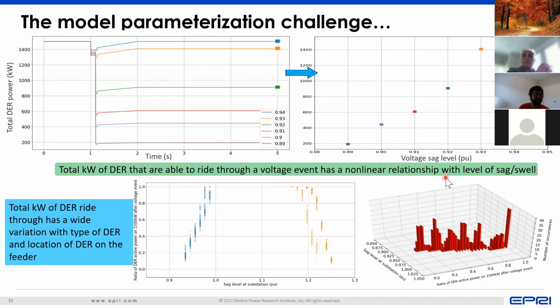So 2003 was in a way when the first IEEE 1547 standard came into play. So the DER that connected after that would follow the 2003 standard. But then there was an amendment in 2014, there was an amendment in 2018, there's an amendment in 2020. So now when you go until 2023, you can have DER that follow all 3 standards spread out across the feeder, and they all have different kinds of characteristics. So the challenge that comes about from the transmission planning perspective is, without really modeling every DER or every feeder in detail, is there a way we can still represent these characteristics in an aggregated format so that we still get a picture of what's happening and also maintain our computational efficiency in running the various studies?